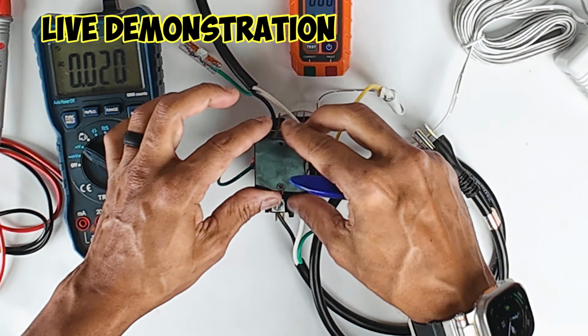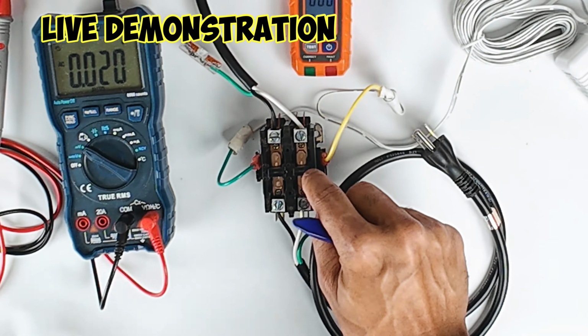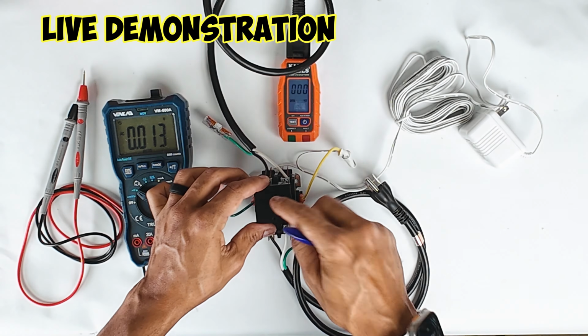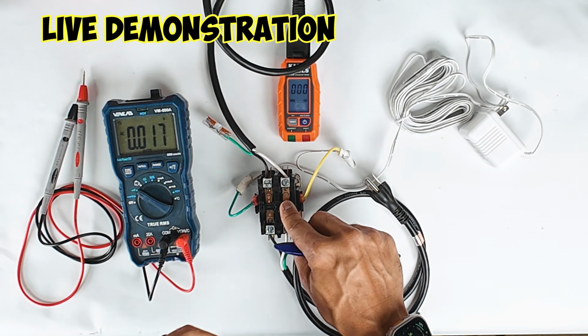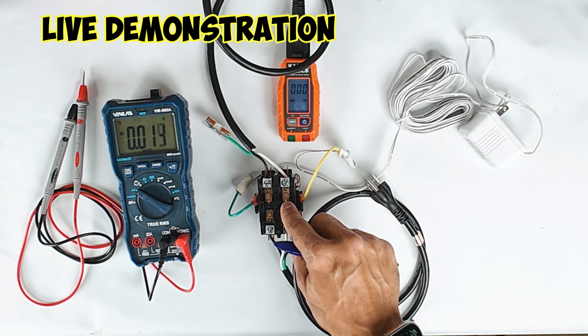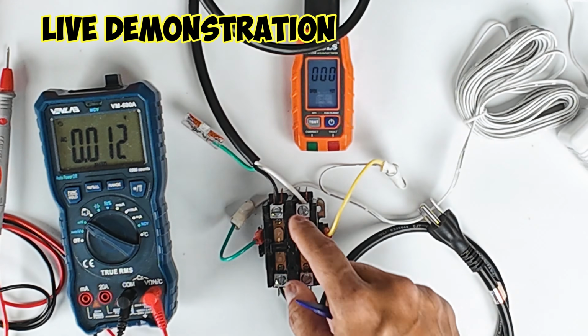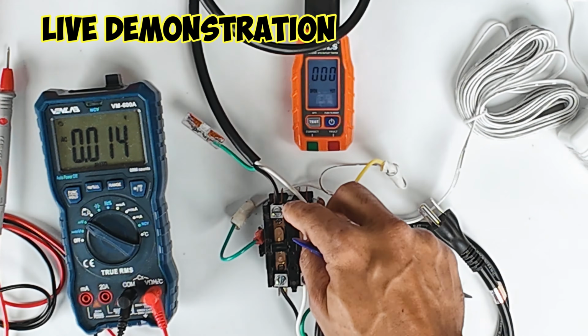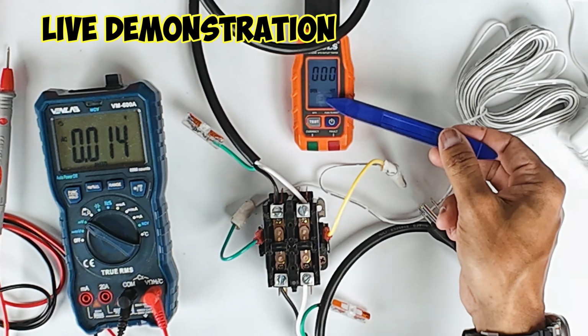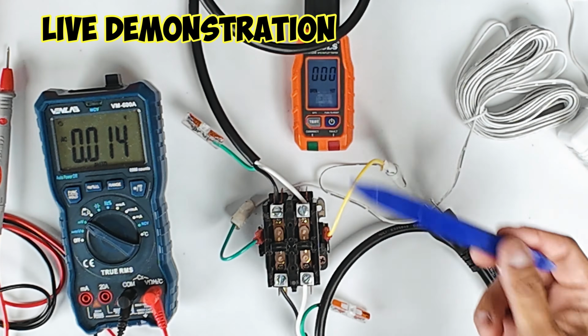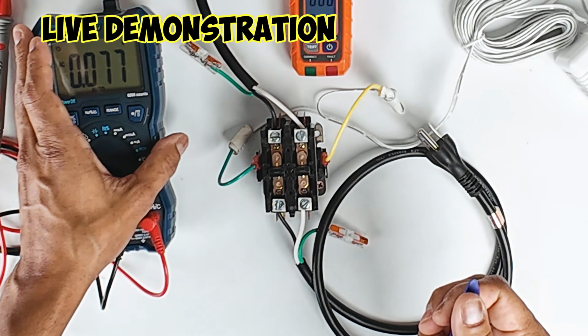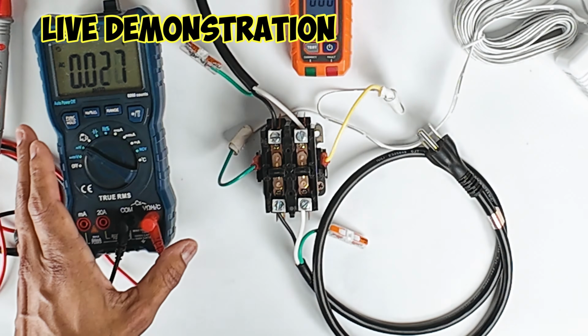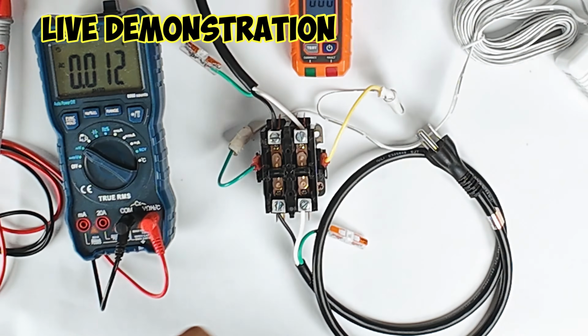And this in the middle here is the manual button on your contactor. Some of you will have a button that's just located here that you can press. In my case, we have a little cap covering the button, but you can remove it and this will activate the button manually. On the top of the contactor, we have the power that's going out, and I have it connected to a meter here so you can visually see, as well as my meter here, which I'm going to use to measure voltages to show you what actually happens during the whole process.